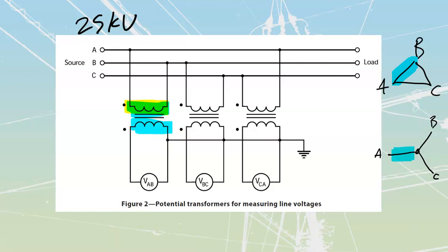If I wanted to connect this thing as a delta type, I would come off of this line over here and then connect over to my B. It then goes through. Here's my transformer. Make a connection from here over to the next one, to my C. And then from here, I would go back across to my first one. At this point, you should be able to trace that through and see that we've got a set of delta connections: A connects across to B, B connects across to C, C connects back across to A.